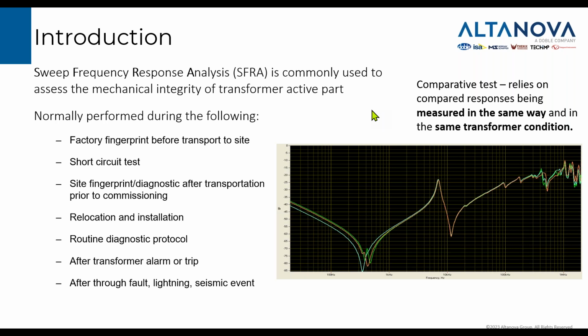But what does a good response actually mean? That means it is as was expected. So we have several methods to assess whether it is as expected or not, and basically we do it by comparison. Here on the screen, the easiest way is to compare the 3 phases. When a transformer is available for testing, all 3 phases are normally available, and we can test all of them and compare. It's not always easy to interpret these results, but it's the easiest way to get them. There are some other options.